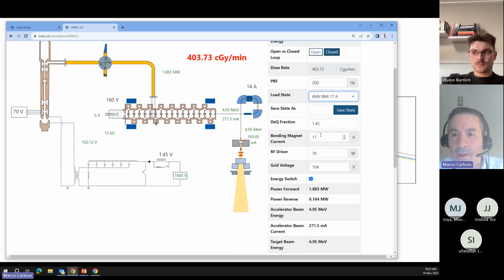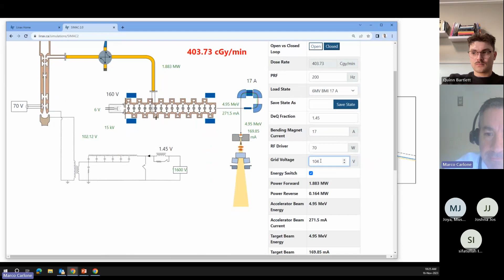So what I've done is go through all the different modes, and rather than going through each one individually, I'll just show one more to show the difference. As an example, we have our photon beam screen here for our 14 MV beam. We have a depth dose of 68% at 10 centimeters. If I change this back to the 17 amp state, which is a higher beam energy, I'm just going to re-enter these to make sure that we have the correct energy.